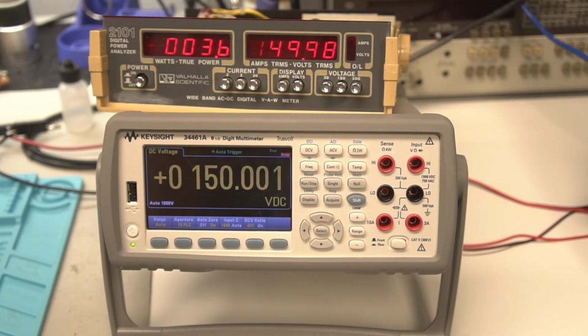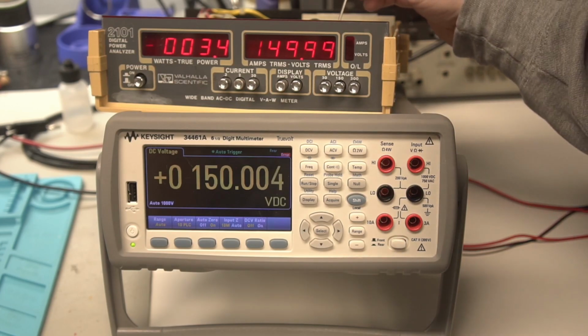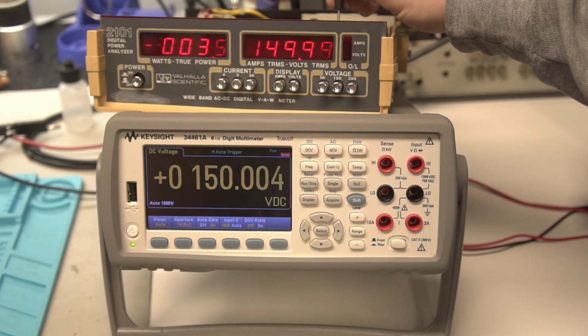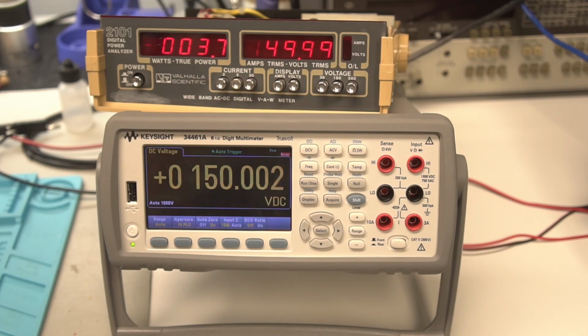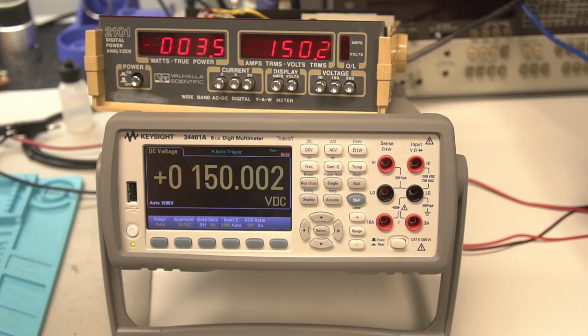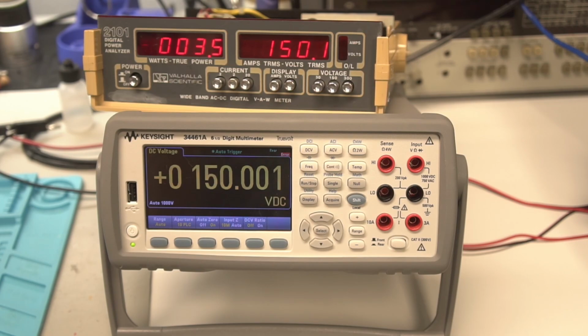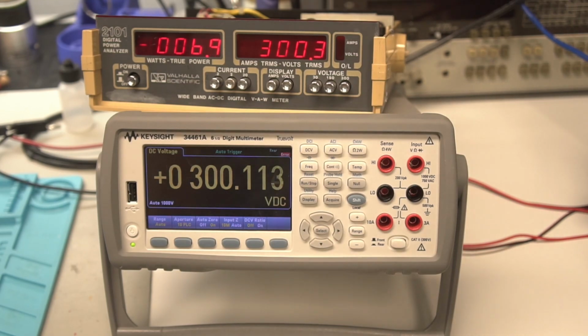Okay, now we need to adjust the 150 volt range, and that is R45, which looks like it's very close. I don't think we're going to beat that. So now we will change into 300 volt range. Should still have about the same accuracy there. But in the 300 volt range, we will go up to 300 volts and check the 300 volt range, and that one adjusts on R49. All right, R49 will have a very small adjustment too. Okay, so now the voltage range is adjusted, and then we just verify it with AC now. So the adjustments are all done in DC, verification is done in AC.